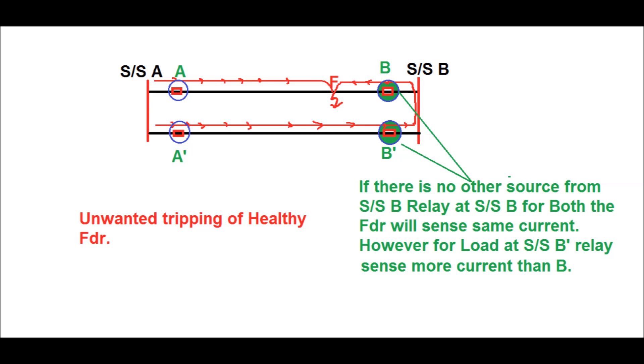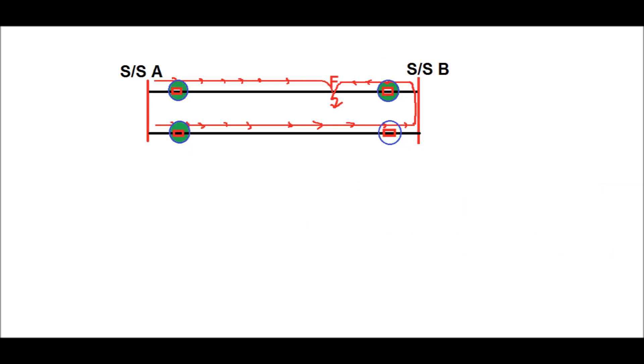This unwanted tripping can only be avoided by giving directional features to the relay. After applying the directional features, under the same fault condition, relay A, relay B, and relay A' will sense the fault current. By giving proper time coordination of the directional relay, we can differentiate the fault and the faulty section will be cleared first by relay A and relay B. If relay B does not clear the faulty section, then relay A' will trip the healthy feeder to clear the faulty section. Therefore, relay A' will act as a backup for relay B.